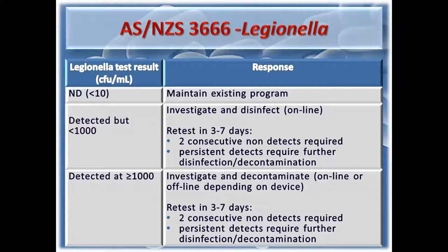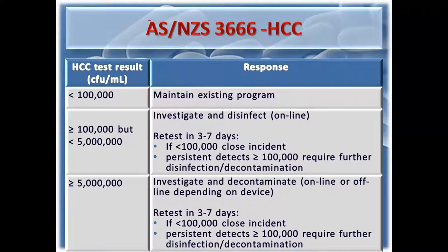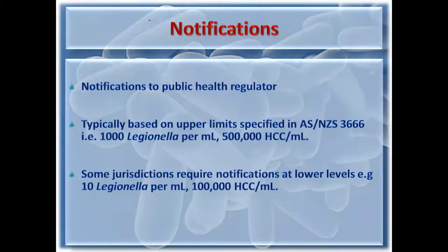Heterotrophic colony counts, similar. Again, we've got ranges much higher now, of course, less than 100,000. A similar program for Legionella, but just at much, much higher levels. Notifications are usually specified... need to go to the public health regulator or to either the state health department or local government. They're typically based on the upper limits specified in the Australian standard. So that is greater than 1,000 Legionella per mil or greater than 500,000 HCC per mil. Some jurisdictions require notifications at lower levels. So for example, 10 Legionella per mil or 100,000 HCC per mil. That's less common.